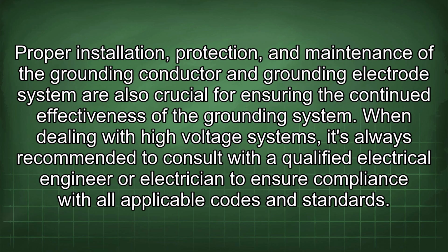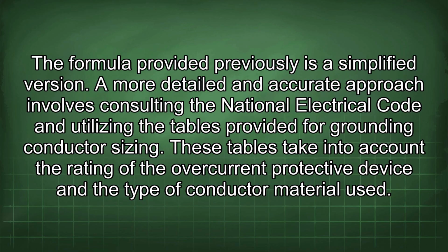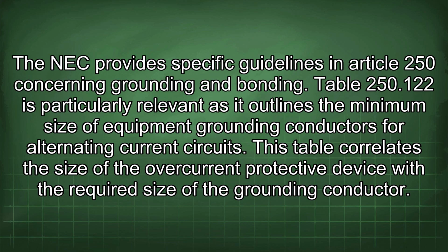When dealing with high voltage systems, it's always recommended to consult with a qualified electrical engineer or electrician to ensure compliance with all applicable codes and standards. The formula provided previously is a simplified version. A more detailed and accurate approach involves consulting the National Electrical Code and utilizing the tables provided for grounding conductor sizing. These tables take into account the rating of the overcurrent protective device and the type of conductor material used. The NEC provides specific guidelines in Article 250 concerning grounding and bonding.